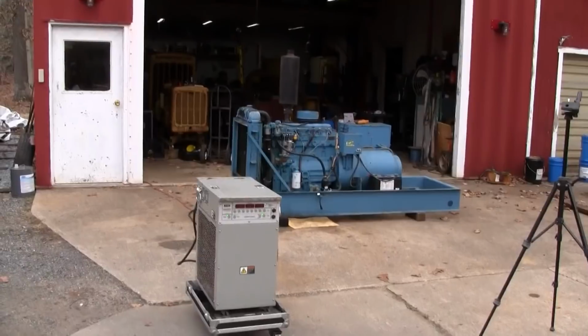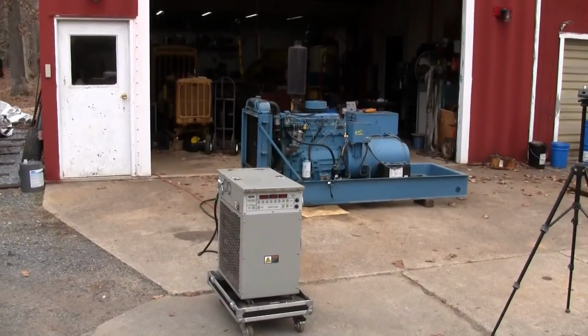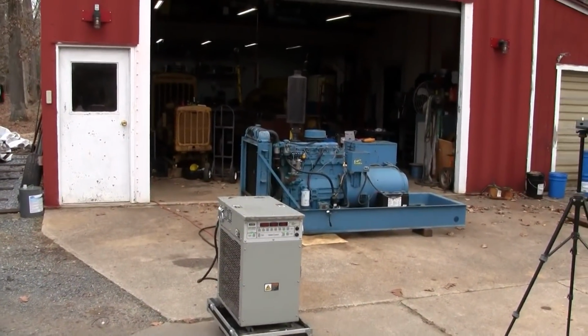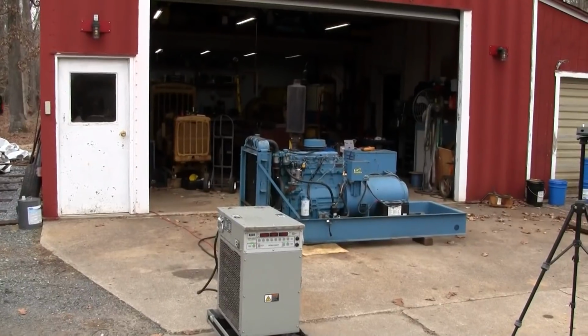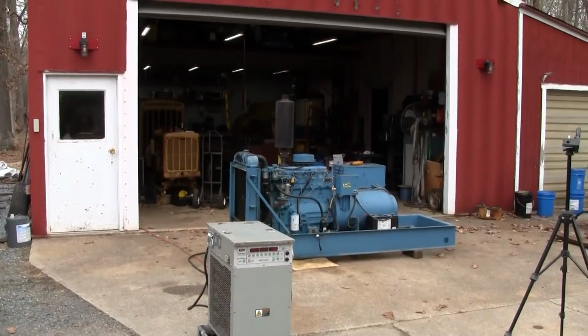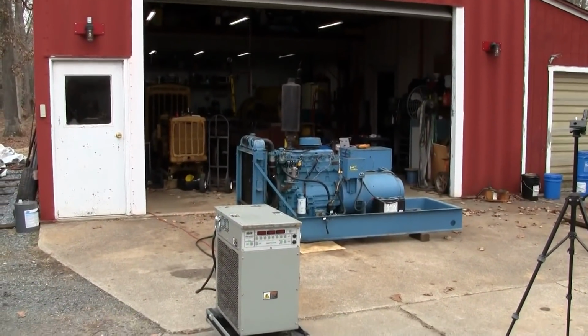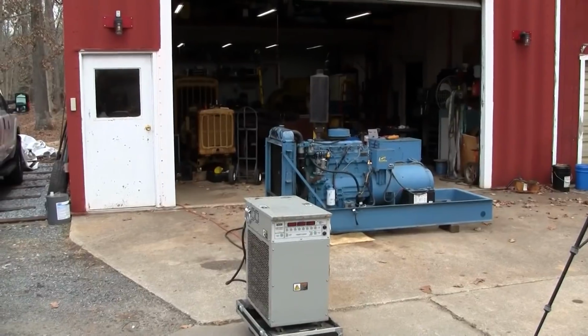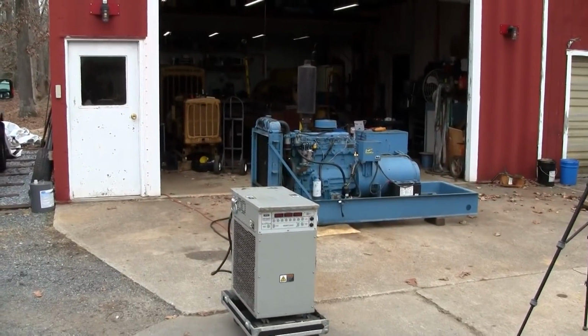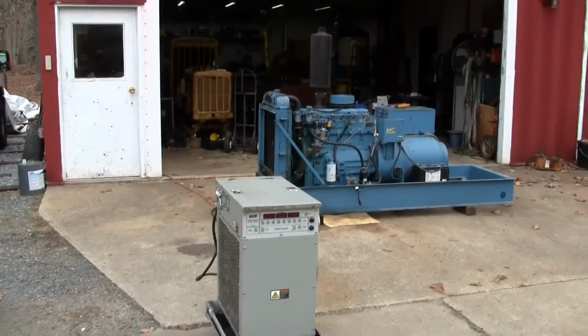Okay, so that right there proves we've got enough horsepower to maintain 60 hertz at 45 kilowatt. We're just under 45, just because that voltage is unstable. Let's crank it up a little bit.